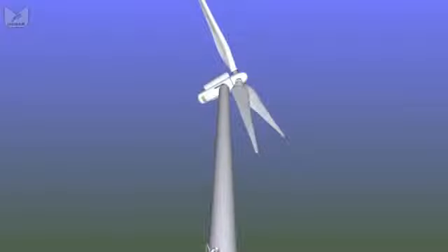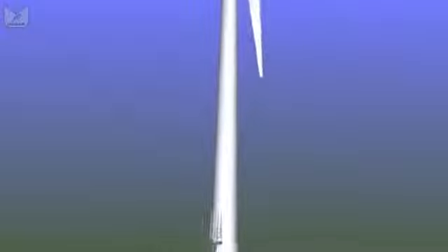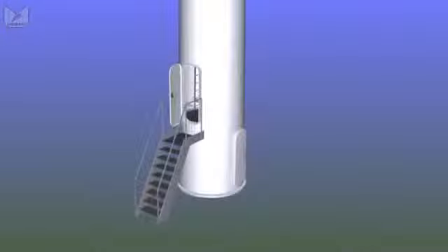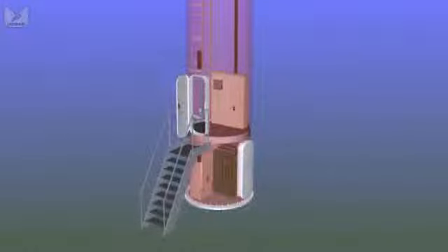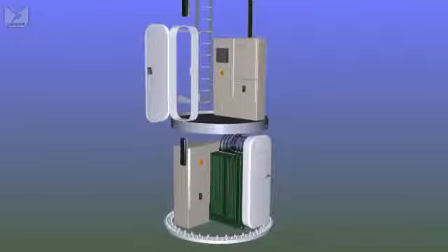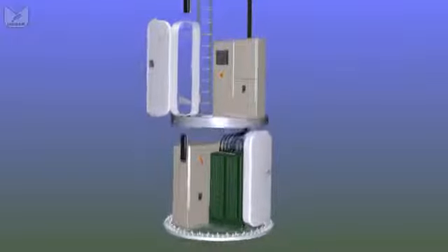Turbines of this type are typically 25 to 45 metres tall, and at the base you will often find two doors. The lower door takes you into a secured compartment where we have a high voltage step-up transformer. The generator at the top of the turbine is producing about 690 volts, and this transformer converts that into several thousand volts to send it more efficiently to the substation. The main entrance to the turbine is at first floor level, and there we find a control cabinet and the base of a ladder, or a series of ladders.